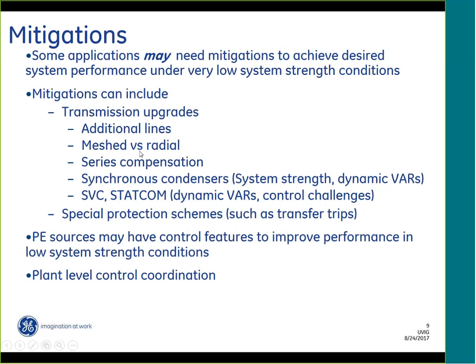Trying to avoid radial systems, or systems that tend to be radial, so that the impact of single contingencies is less severe in the system strength. Using series compensation tends to counteract the effect of the line inductances, and by doing that, you're basically also making the voltages stronger. You're increasing the system strength.